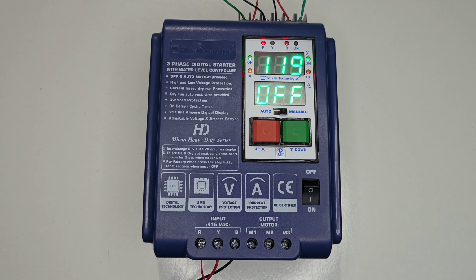Now I'll explain what this dry run reset time is. Once the motor trips in dry run condition, then after how much time it should start again to check whether it is dry or not. That time is known as the dry run reset time, and you can adjust it in minutes.